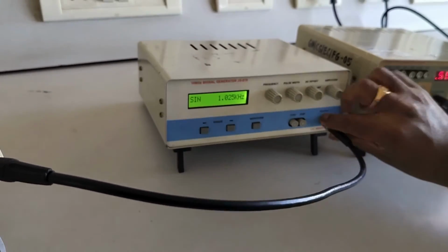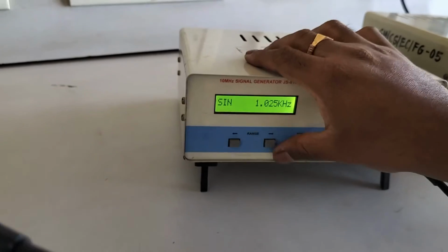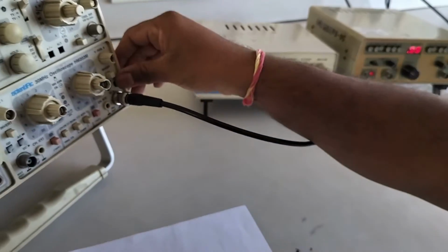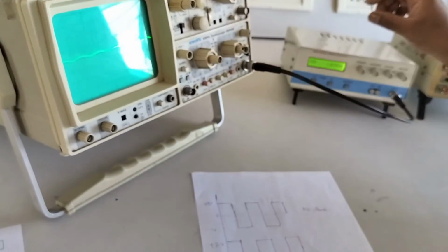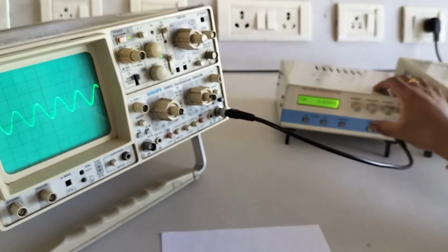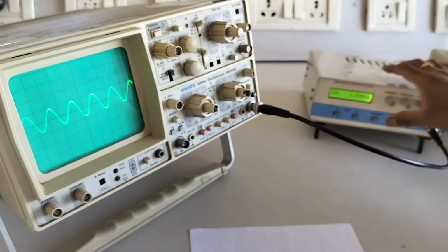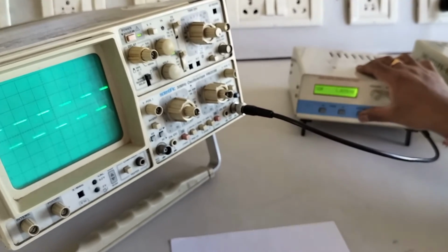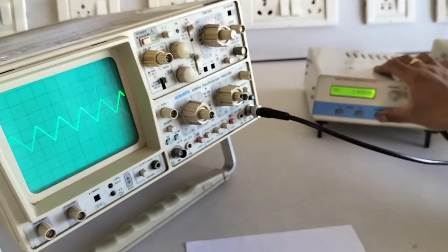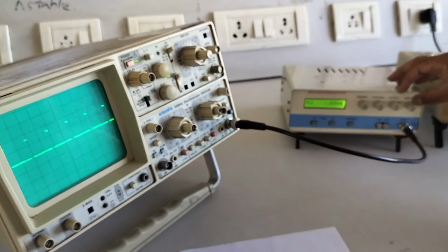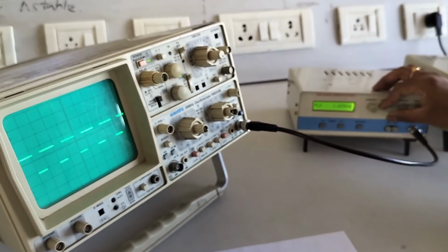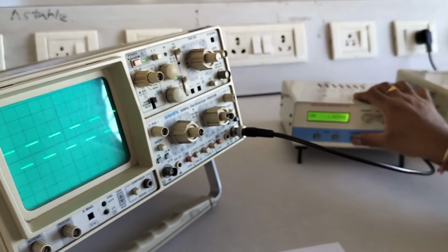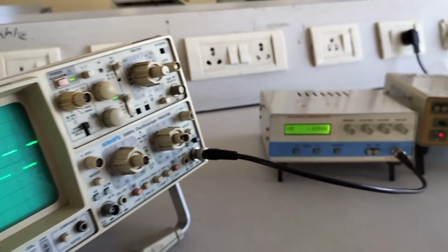See here. Here the range I have given with these micro switches. Here also the same attenuation buttons are there, 20 dB, 40 dB. For waveform in this function generator you can select here. They have given waveform buttons: sine, square, triangle and pulse. Pulse also is a common thing, the pulse width you can change here. In the previous one the waveform sine, triangle, pulse was on only one button. In this case they have given 4 push buttons.